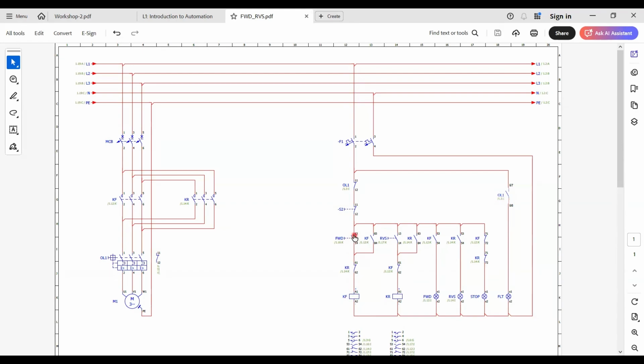So once you press the forward contactor and the reverse contact is turned off, this KR, the normal closed contact is closed, and that will energize the forward contactor coil. So that will allow the auxiliary point 83 and 84 to this normally open contactor to close, and based on that the coil is latched. Even when you release the forward push button, this contactor coil is self latch using this KF1 auxiliary point.